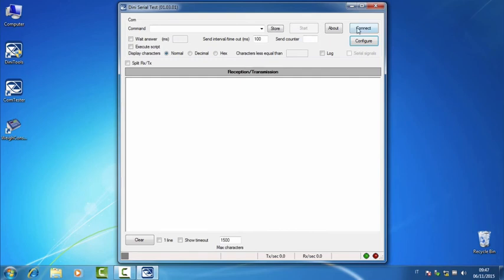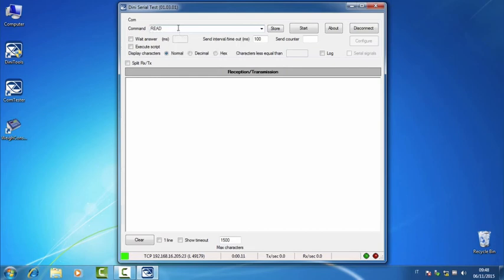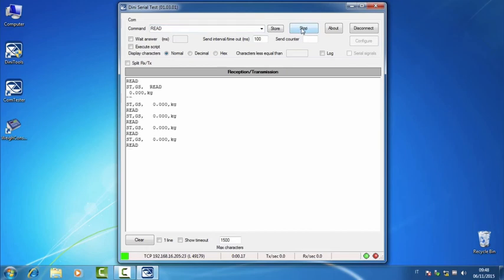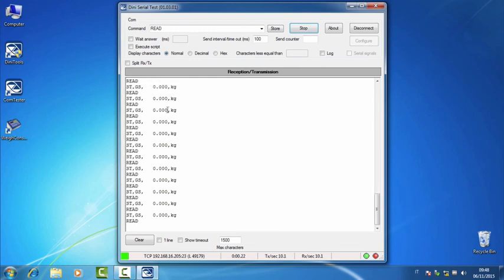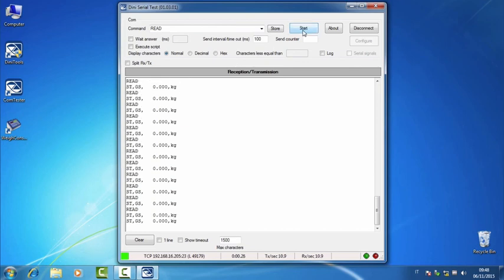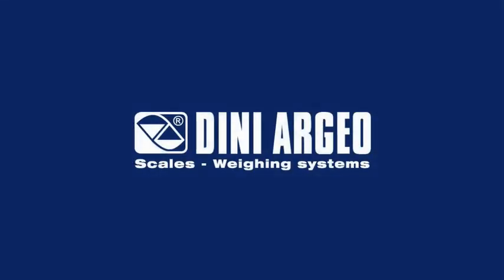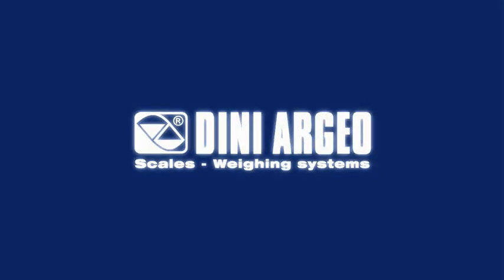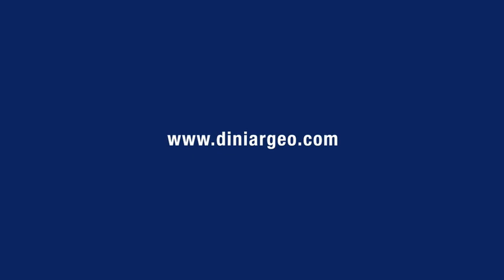Now we click on Connect and the green LED will appear. We edit a command in capital letters, for example READ, and we click on Start to send it continuously. We can see that the indicator is answering correctly. So the scale is transmitting the weight. Thank you.